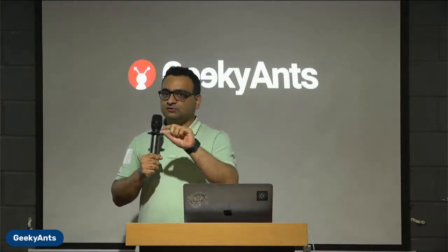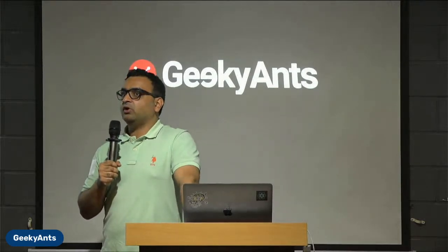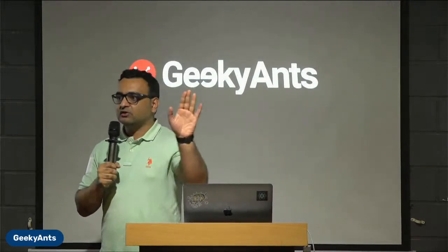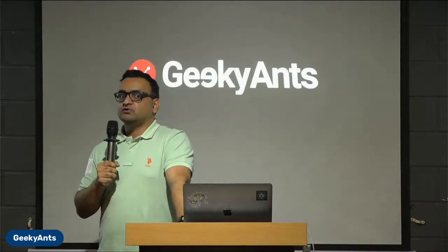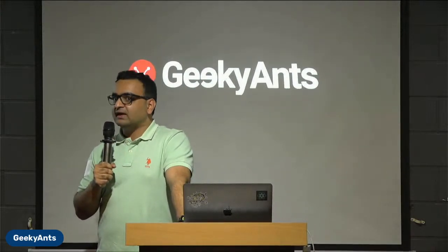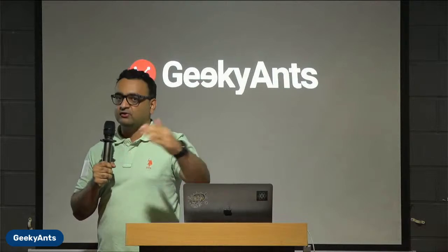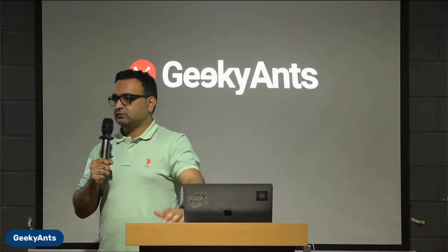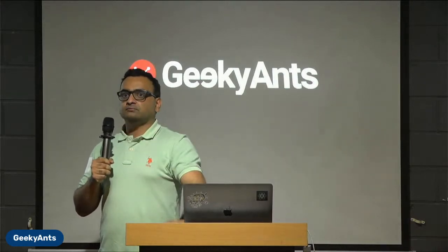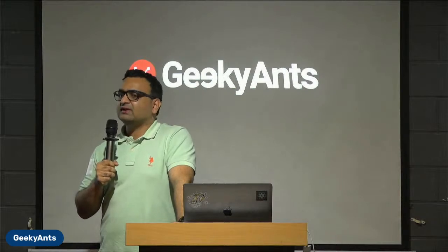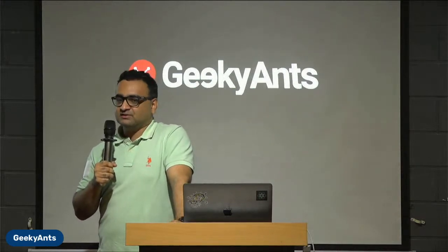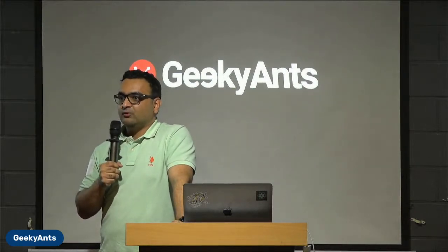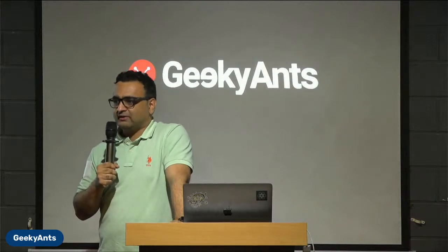Yeah. So as per FDA at least, and again, please take this with a pinch of salt. This might be different for different markets. But for the US, for example, you're not allowed to retrain an AI model once it's deployed. So federated learning is out of the question, for example, right? You have to go through a clearance again if you're using a new data set, for example, or you're adding to the data set. You have to go through a kind of clearance cycle again. So that's a limitation you have to live with. And the reason is, of course, it affects the patient's life at the end of the day. So they want to be very sure, and I guess it's right.